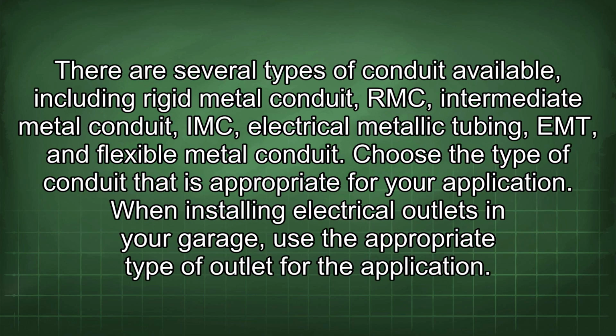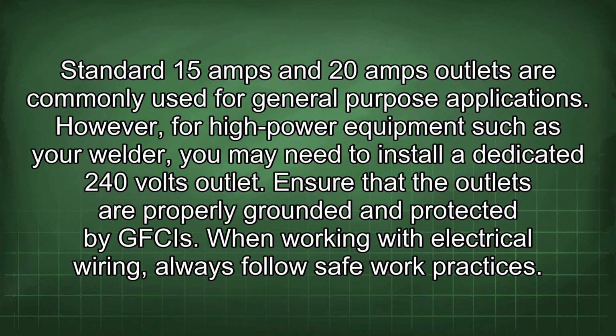There are several types of conduit available, including rigid metal conduit, RMC, intermediate metal conduit, IMC, electrical metallic tubing, EMT, and flexible metal conduit. Choose the type of conduit that is appropriate for your application. When installing electrical outlets in your garage, use the appropriate type of outlet for the application. Standard 15 amp and 20 amp outlets are commonly used for general purpose applications. However, for high power equipment such as your welder, you may need to install a dedicated 240 volt outlet.